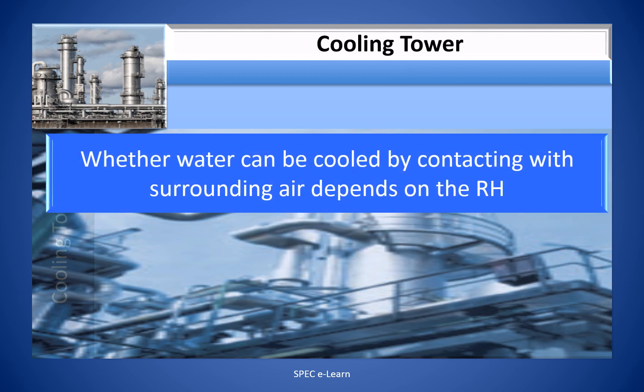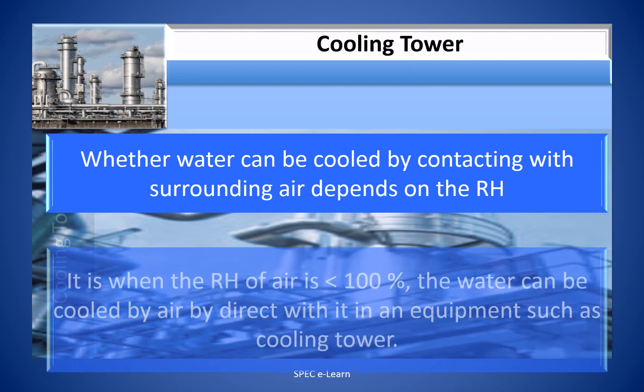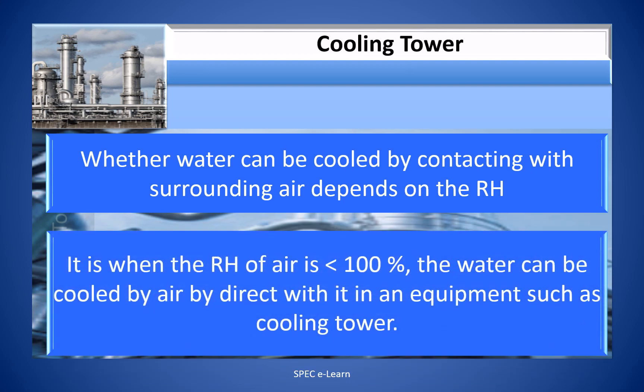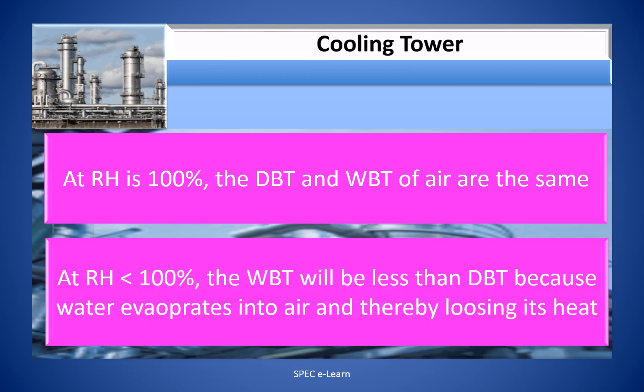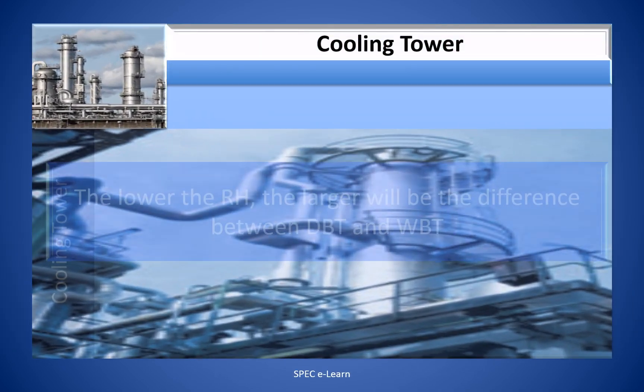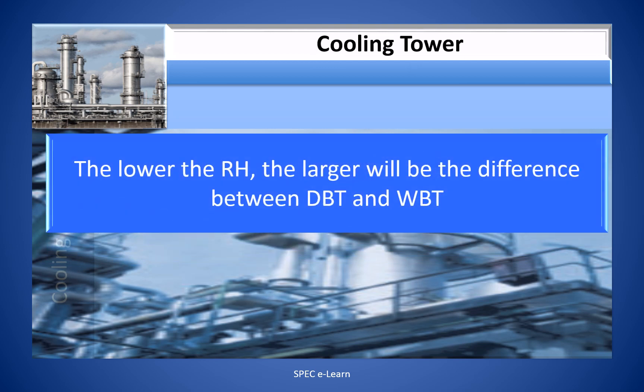Whether water can be cooled by contacting with surrounding air depends on the relative humidity. It is when RH is less than 100% that water can be cooled by direct contact with air in equipment such as a cooling tower. At RH equal to 100%, DBT and WBT of air are the same. At RH less than 100%, WBT will be less than DBT because water evaporates into the air, losing heat. The lower the RH, the larger the difference between DBT and WBT.